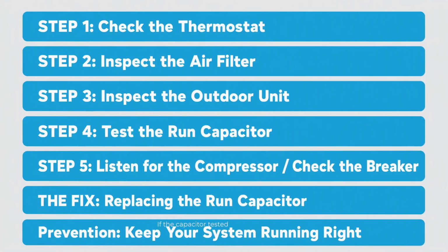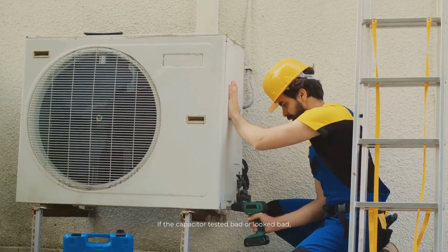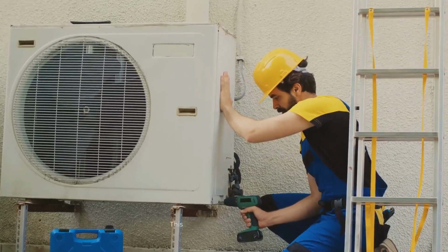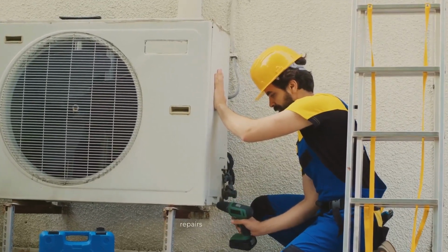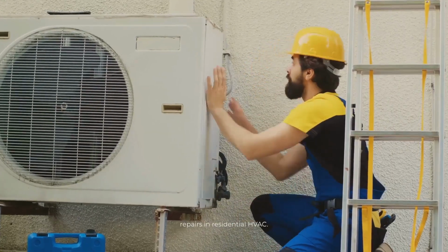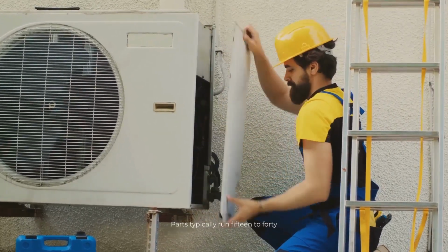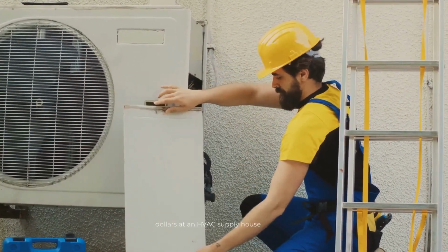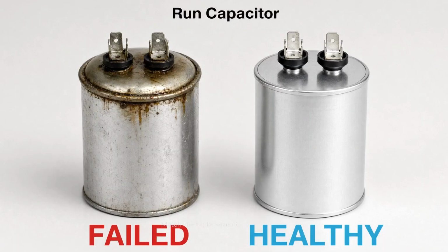If the capacitor tested bad or looked bad, here's the good news. This is one of the most accessible repairs in residential HVAC. Parts typically run $15 to $40 at an HVAC supply house or online. Match the replacement to the original. For a dual-run capacitor, you'll see 2 MFD values on the label, something like 45/5. Match those exactly. For voltage rating, match it or go higher, never lower.